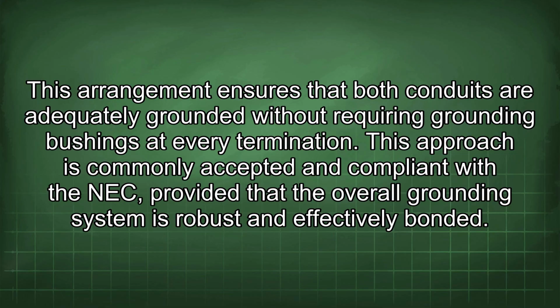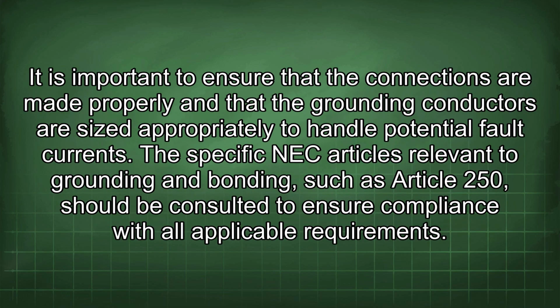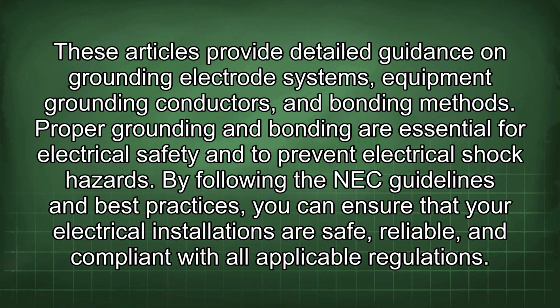This approach is commonly accepted and compliant with the NEC, provided that the overall grounding system is robust and effectively bonded. It is important to ensure that the connections are made properly and that the grounding conductors are sized appropriately to handle potential fault currents. The specific NEC articles relevant to grounding and bonding, such as Article 250, should be consulted to ensure compliance with all applicable requirements. These articles provide detailed guidance on grounding electrode systems, equipment grounding conductors, and bonding methods. Proper grounding and bonding are essential for electrical safety and to prevent electrical shock hazards.